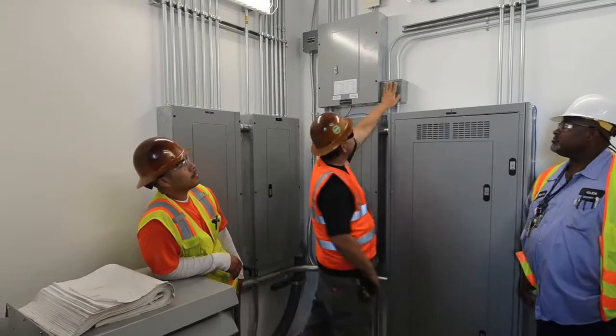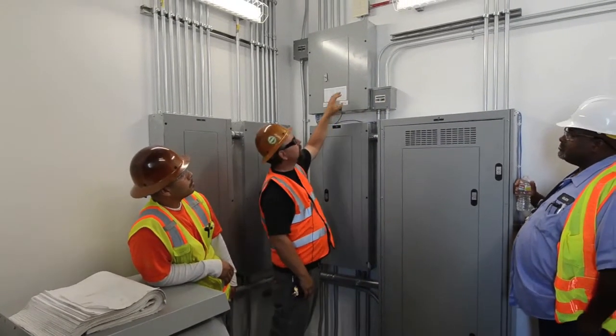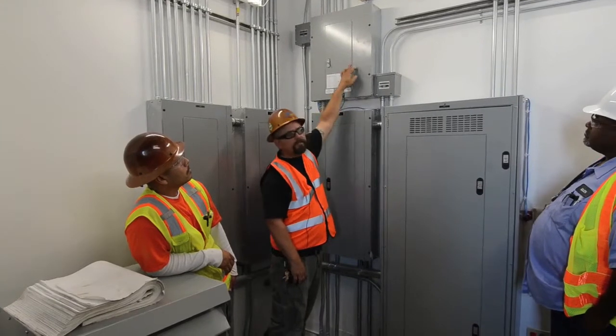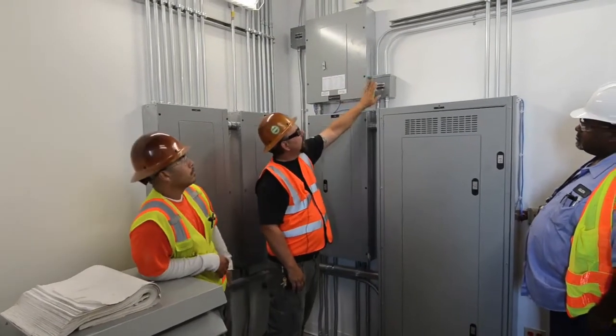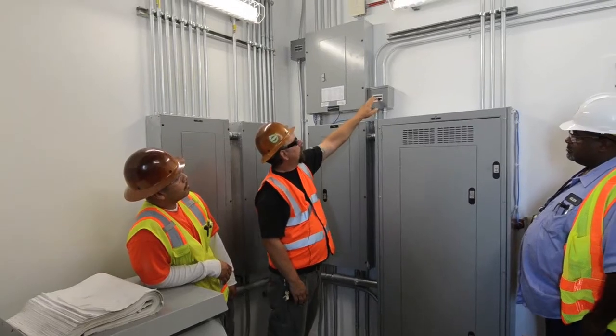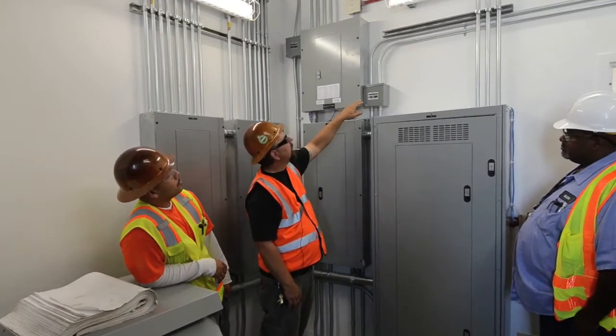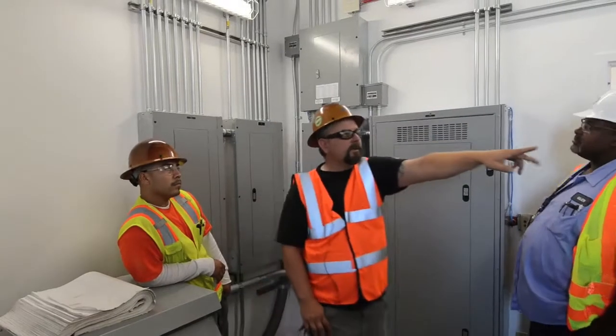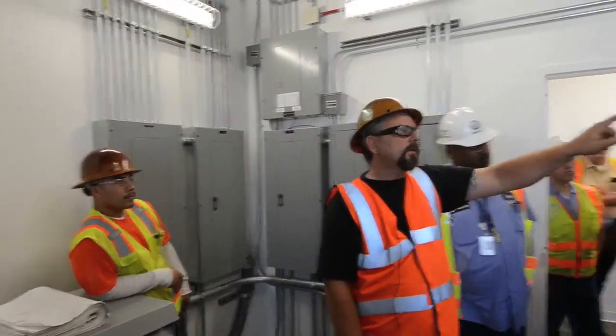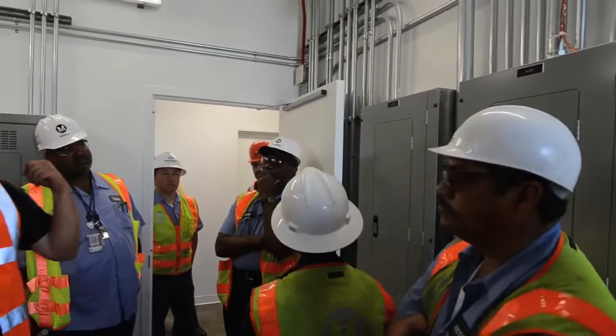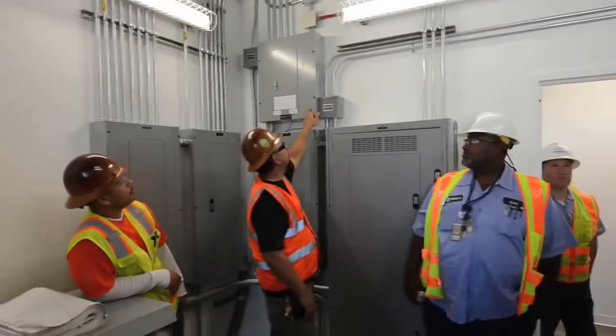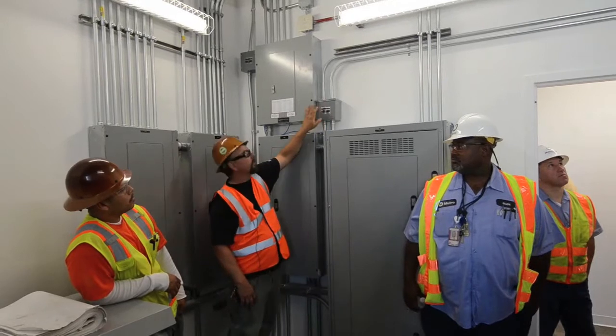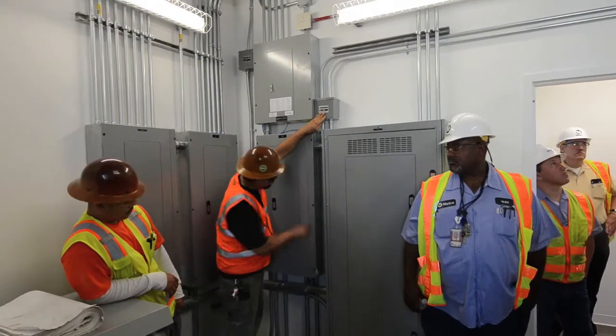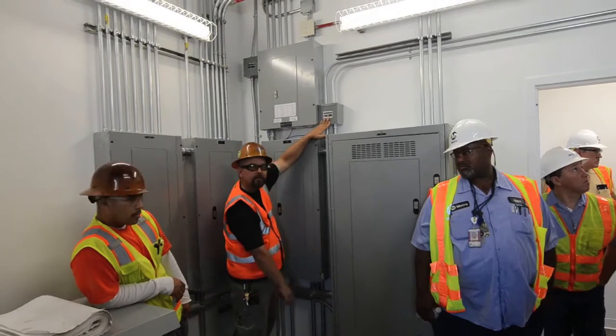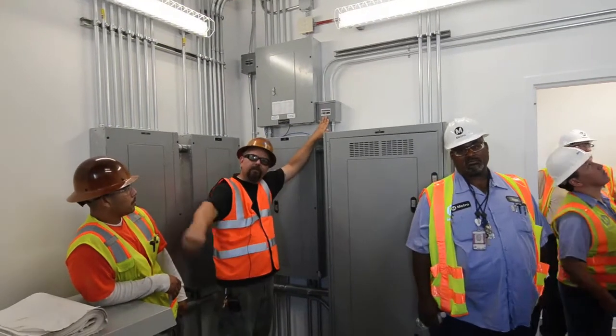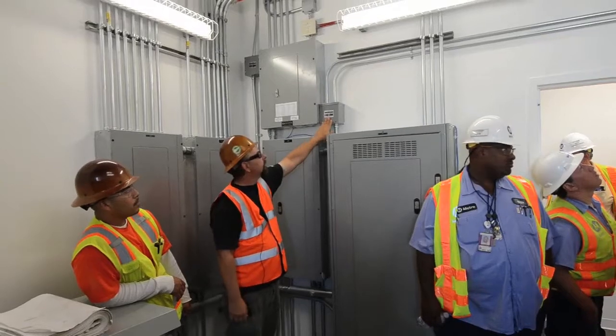Okay, this little box here, remember how down in the main electric room I was telling you guys that there's a divider in there for your emergency circuits? This is how we got the emergency circuits into that corner. So we're piped over here to this emergency panel right behind this gentleman. The emergency lights that are controlled with the lighting control panel are going into the panel from right here. Then the emergency circuits that we're controlling through this panel go down to the garage, down these pipes here, and make their way across that open area like I was showing you guys.